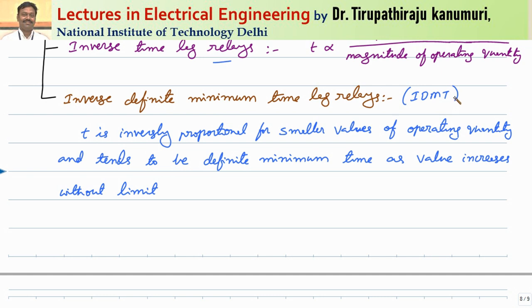That is why the relay should wait for two or three cycles before responding to a fault, which is why we always go for inverse definite minimum time lag relays. The inverse characteristic is justified because the severity of a fault depends on I-squared-R loss, heat produced, and forces between adjacent conductors — all proportional to the magnitude of fault current. If the fault magnitude is more, the severity is more and it should be disconnected as early as possible.